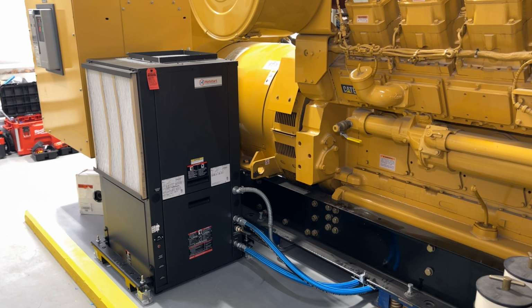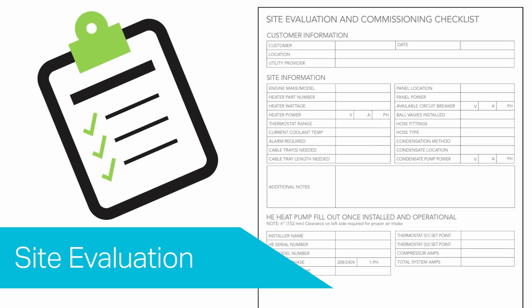After the thermostat has been set, allow the HE system to start and verify coolant temperature is increasing. The time required for initial heating of the unit to the set point will vary depending on ambient temperature and engine size. After the temperature rise has been observed, be sure to complete Hotstart's site evaluation and commissioning checklist.